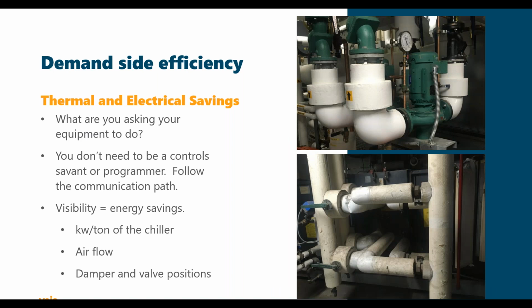Within that demand, I consider all of the distribution - fans, pumps, chilled water coils, heating coils - and it's not the fans and pumps that are inherently inefficient. The efficiency gains come with the communications, and we could spend hours talking about controls and programming, but you don't have to be a controls expert to find opportunities. If you have a basic understanding of the graphical interface and what the customer has visibility into, you can see when pumps and fans are not modulating and not load matching.